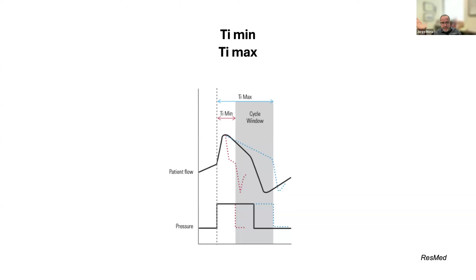The TI min is the time that we define from the beginning of inspiration to whatever TI min we define. And that time, in ResMed devices and these other devices, is mandatory. What I mean by this is it will act in practical terms as a PC breath or a time breath. So regardless of what happens, and regardless of what the flow decrease is, the TI, the pressure you decided, is going to be exerted. After that, there is a cycle window where effort and resistance and everything will take place, and that's the time between TI min and TI max. And once you have reached TI max, if you have not achieved the decrease in flow that is necessary to cycle, you will cycle regardless.